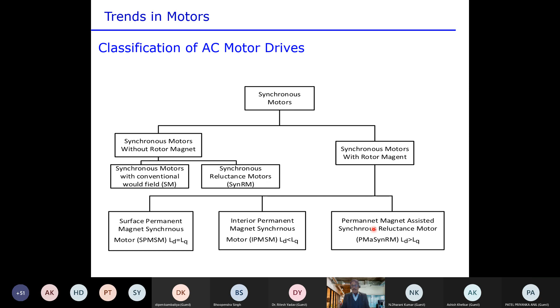This synchronous motor with rotor magnet can be surface, interior, or permanent magnet assisted synchronous reluctance motor. If you look at the classification based on magnet and reluctance torque, from surface SPMSM to synchronous reluctance motor, the magnet proportion reduces from highest to lowest. Similarly, the reluctance torque increases from zero to maximum. So in a synchronous reluctance motor, full torque comes from reluctance and zero from the magnet.